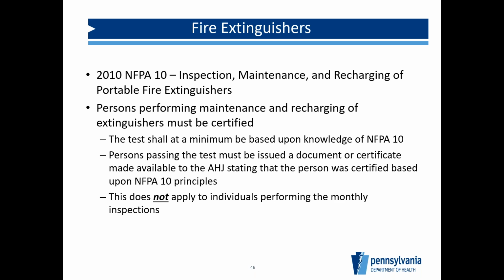So if you're doing any type of maintenance, recharging of the extinguishers, you have to be certified with some type of NFPA 10 training. NFPA 10 is the authority on fire extinguishers. So if you're doing the monthly quick checks, you're fine. You just need to be trained to know what you're looking for. But anyone that's coming in to do the annual needs to have that certification.